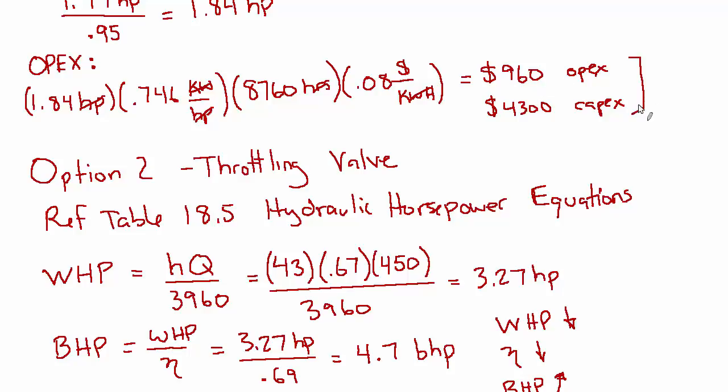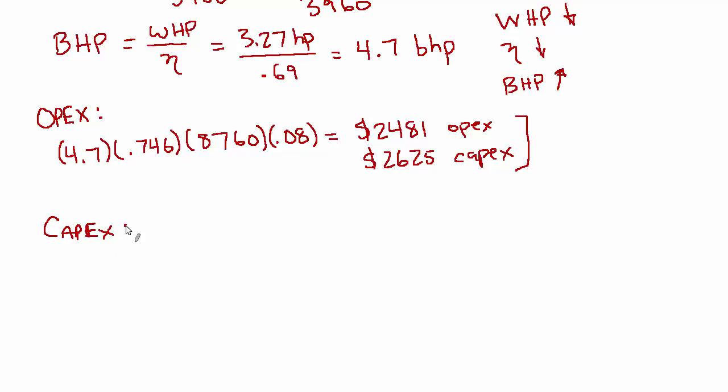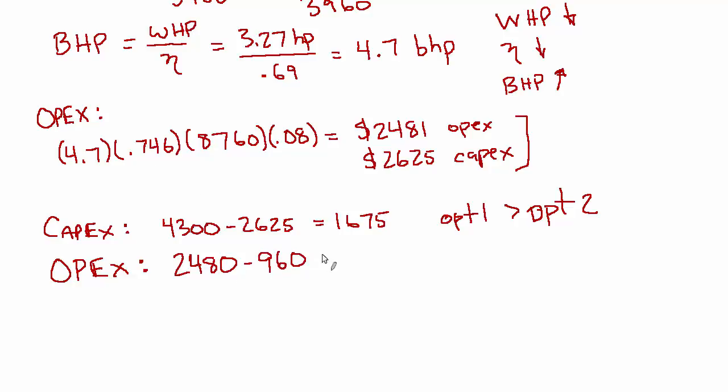So these were the results of our option one analysis. And these were the results of our option two analysis. And now let's find the difference between the two. Starting with the upfront cost, we have 4300 for option one minus 2625. So 1675, that's how much more option one costs than option two. But then on the OPEX side, we have a cost of 2480 every year with the throttling valve, but only 960 if we do the VFD.